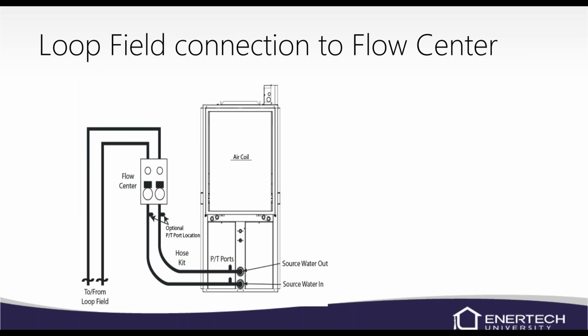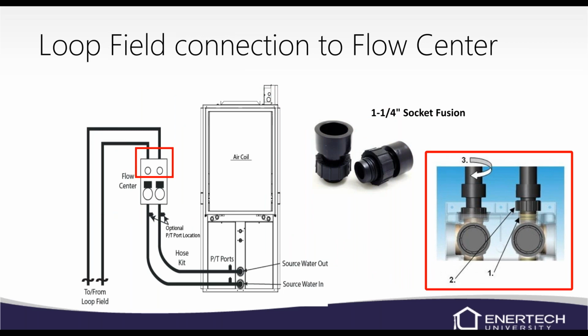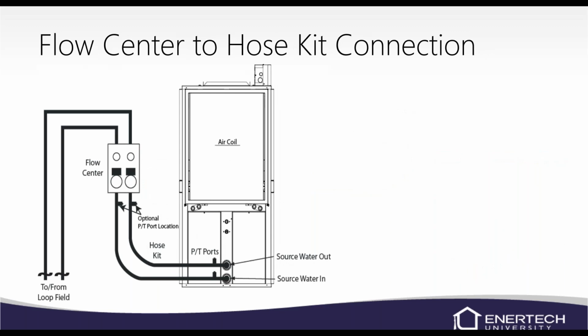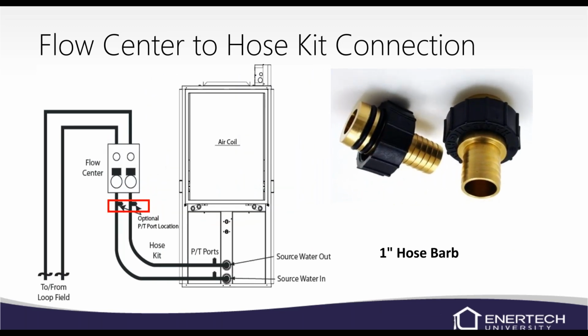Loop field connections to the flow center. Again, those are normally going to be your PE pipe, so it's going to be a 1.25" socket fusion fitting. And then at your flow center, more than likely, it's going to be these hose barb fittings. When you order your hose kit, you can order them with the PT, and it'll have a plug in where the PT goes. It'll come with the PTs. You have to put them into the fitting, but I would recommend that you just order the fittings with the PT port adapter in it, so that you don't have to put them in the pipe somewhere else. And to be honest, I don't care if the PT ports are at the flow center or they're at the unit. It doesn't really matter to me.